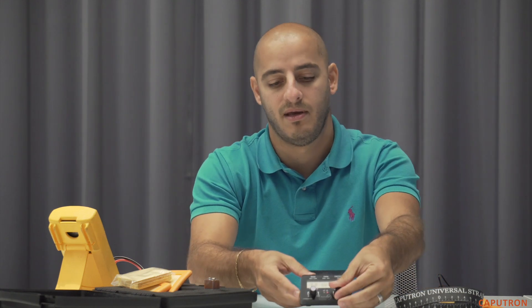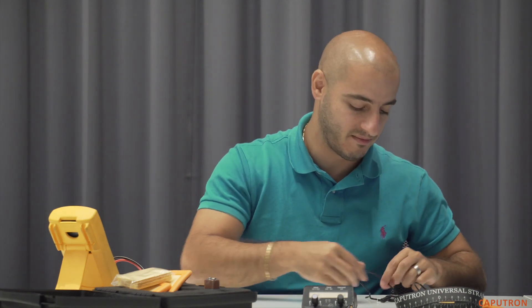You will notice at this point the device is beeping and the screen displays 'electrode recheck.' What this means is that the electrodes are not connected, or if the electrodes are connected, you do not have optimal contact quality and should adjust the electrode positioning. Remember, you will also need to use saline solution — we recommend 0.9%.